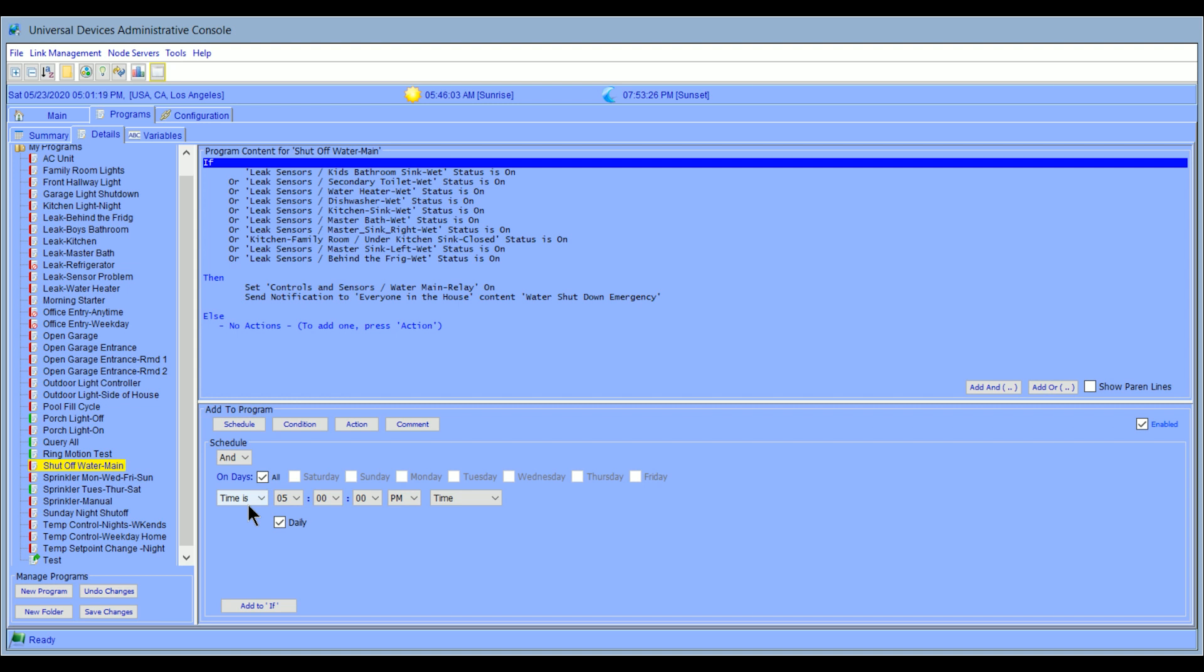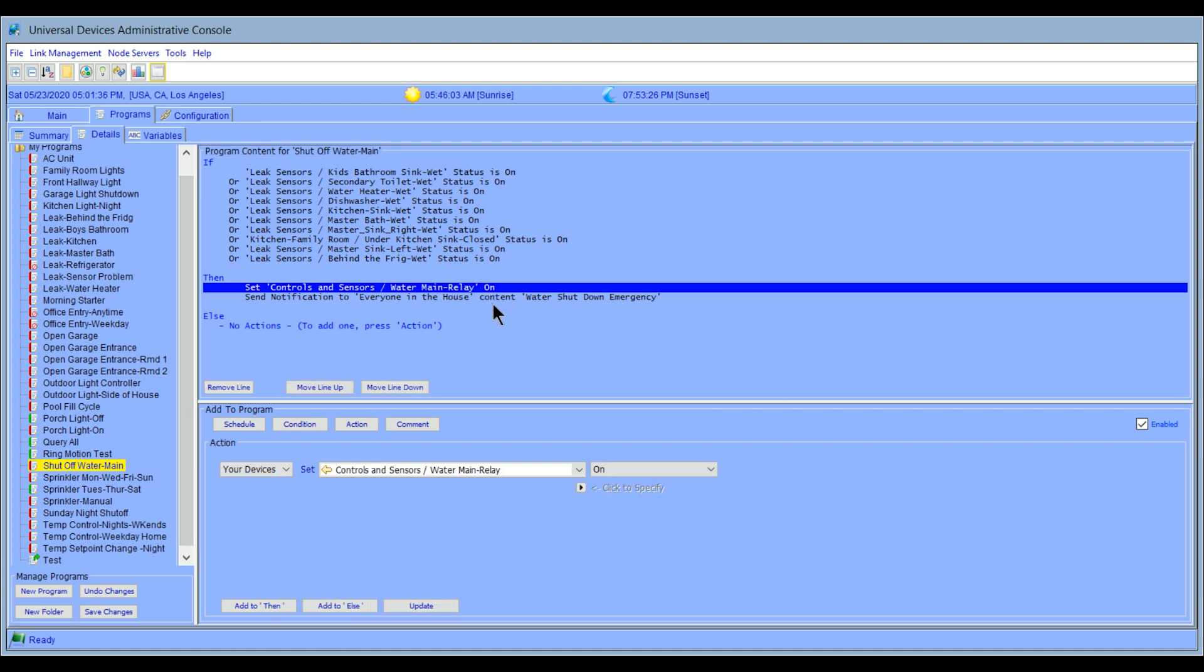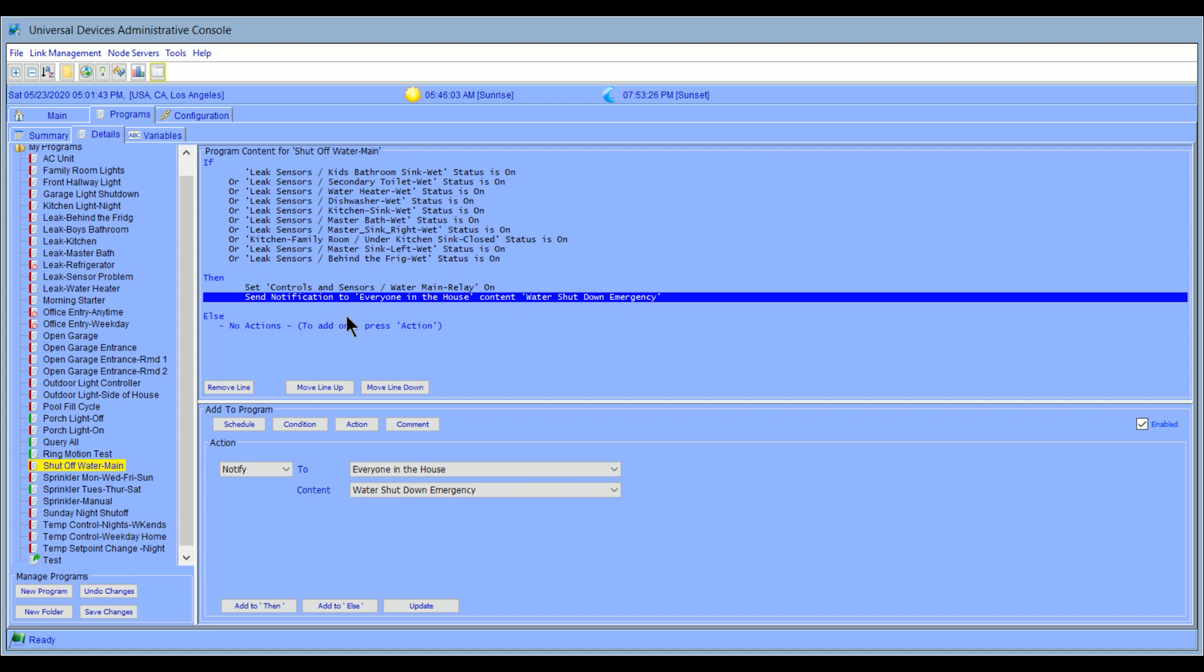But I've also added an auto main shutoff. So I've added a water valve on my main line that actually shuts off when it gets a signal. So this program, all it really does is it says, if I get an on condition from any of the sensors, basically if a sensor's tripped, there's water there, and it gets an on condition, it's going to actually activate this main relay. It's going to turn it on, which means it's going to turn the valve off. It's activating the valve. And it's going to send a notification to everyone in the house that there is a water shutdown. It's not going to turn it back on. It's just going to stay in that position.